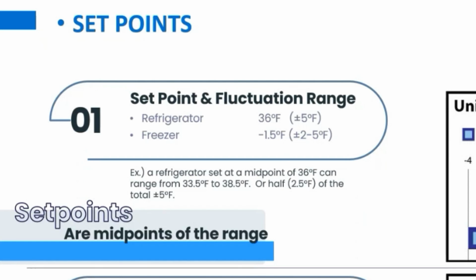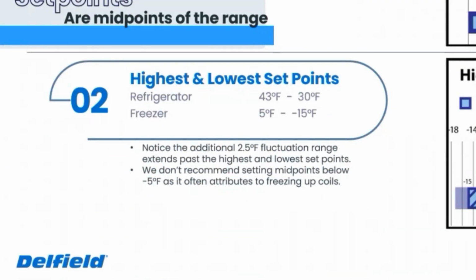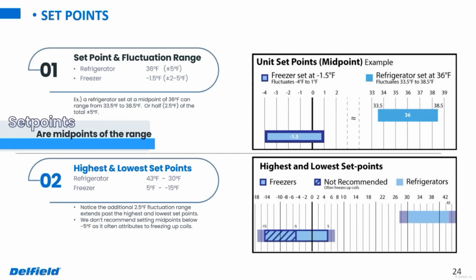With the freezer, those are normally going to be set in that 0 to -2 range, which keeps us in a pretty good space as far as the set point goes. You'll notice the high and low set points towards the bottom of the left-hand side illustration, where it'll have the refrigerator cycling between about 43 and 30. And then the freezer, some of our freezers can actually go down to -15 degrees on the control. There aren't too many scenarios where I would envision it needing to be set down that low. One maybe is if it's a freezer that's getting opened a time or two a day and they're storing ice cream in there, and they want to keep that ice cream nice and hard.